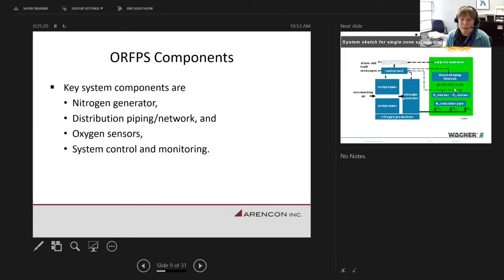So I'm going to come up with an illustration, just a schematic borrowed from Wagner, who's one of the suppliers of these systems. Our key components are, first, a nitrogen generator. The nitrogen generator takes ambient air, separates the oxygen component and the nitrogen component, discards the oxygen component, and filters the nitrogen, so that the nitrogen-rich air at this point is 95 to 98% nitrogen. That's what's going to be put into the protected area. To get it into the protected area, there's distribution piping and a network for the injection into the space.